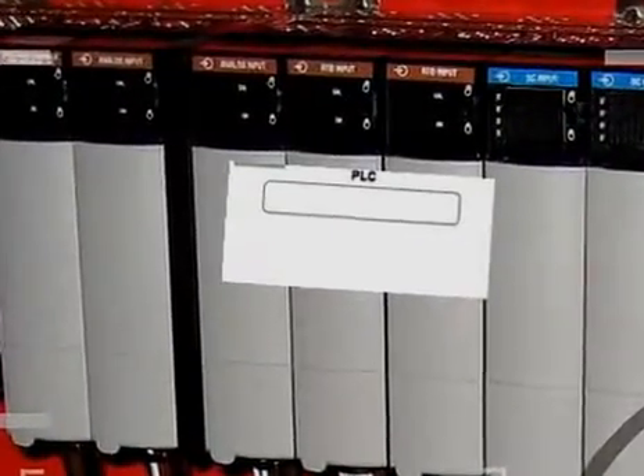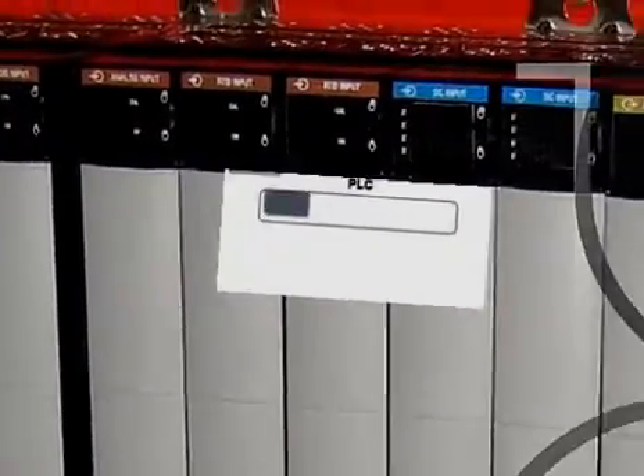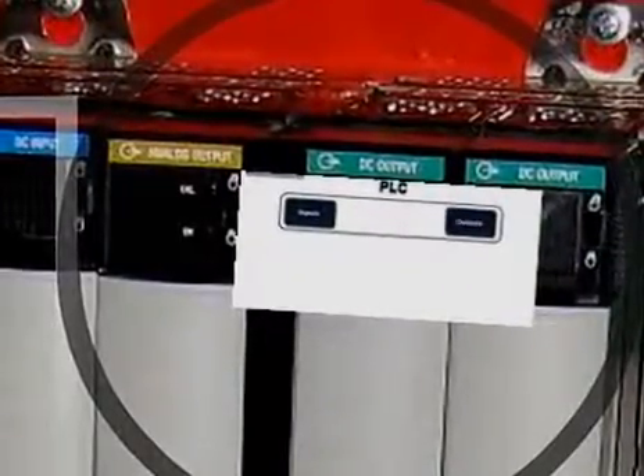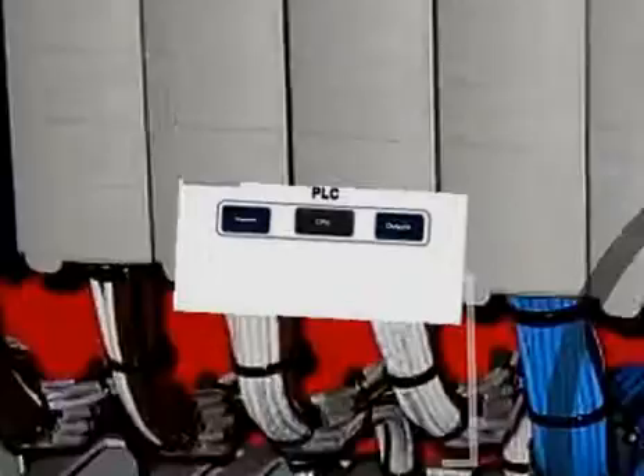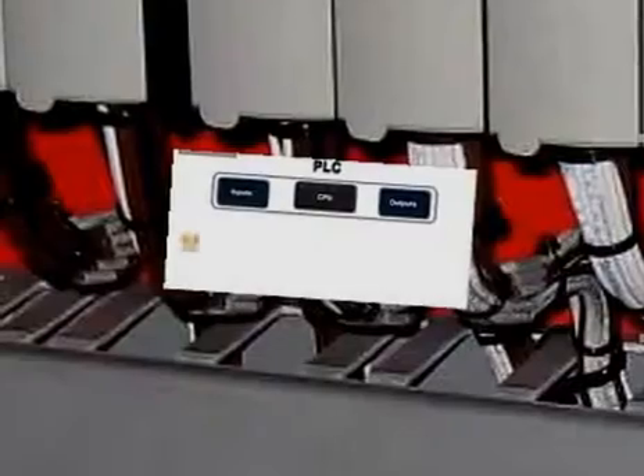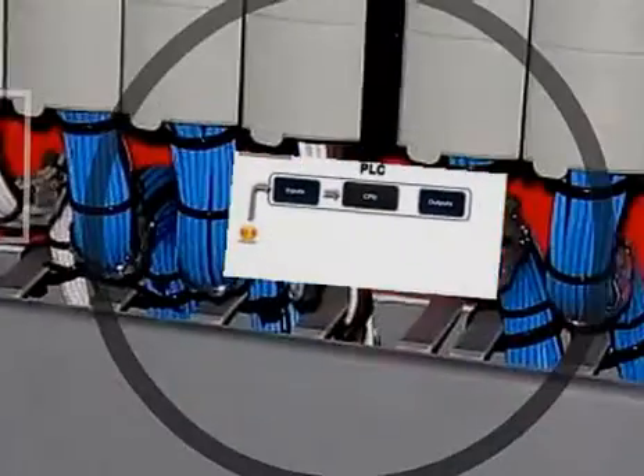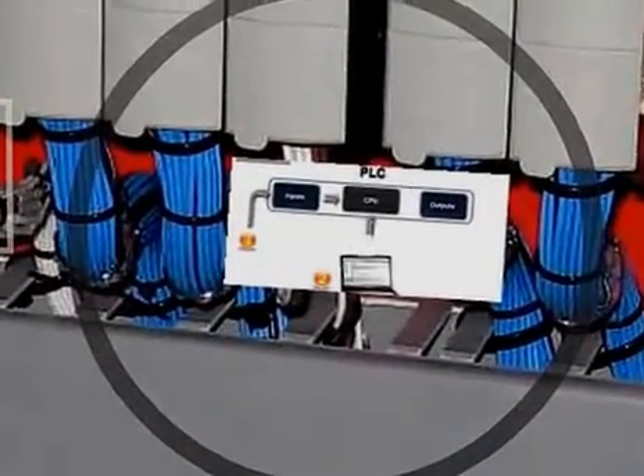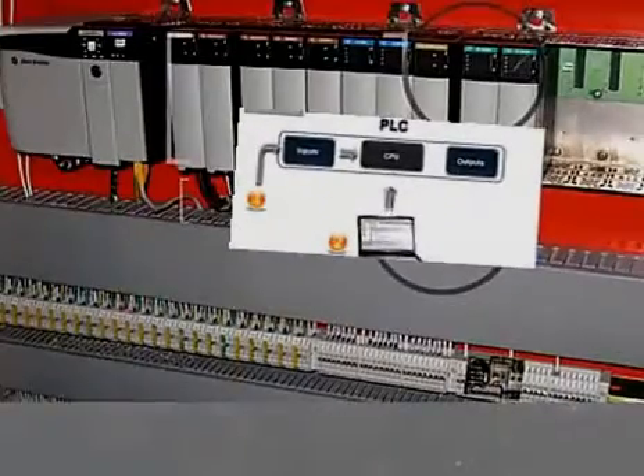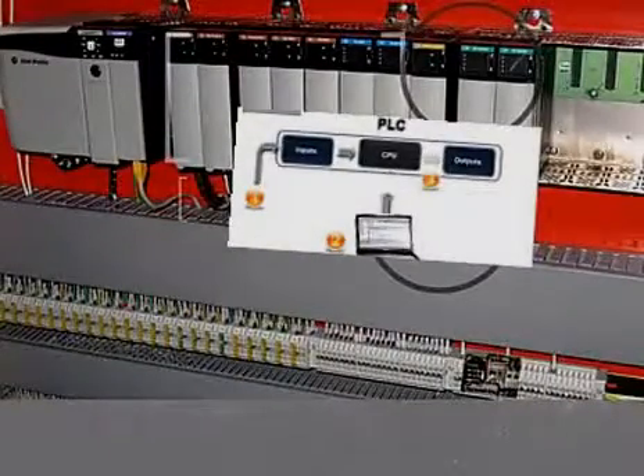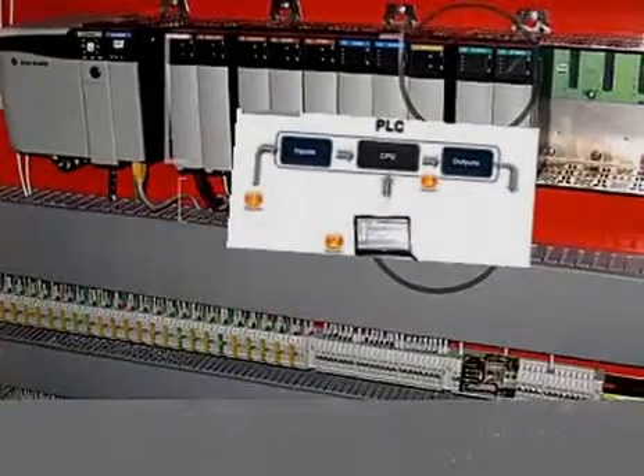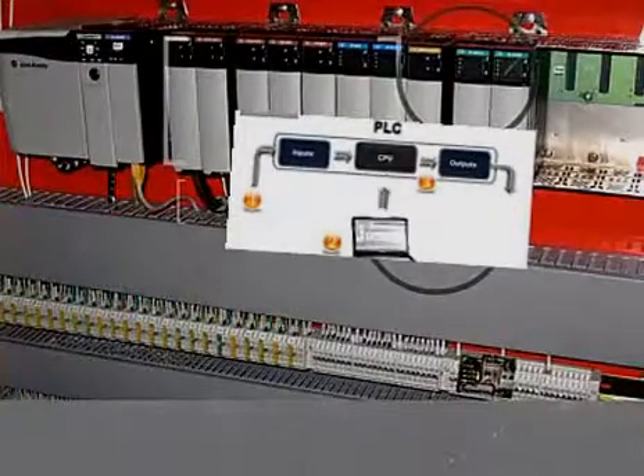A PLC can be viewed as an industrial computer that has a central processor unit, memory, input-output interface, and a programming device. It accepts data and status information from various sensing devices like limit switches and proximity switches, executes the control program stored in the memory, and gives appropriate output commands to devices such as solenoid valves, switches, etc.